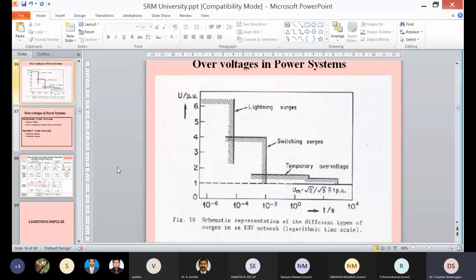In case of switching surge or switching transient, the rise of voltage will be in the range of 2 per unit to 4 per unit. In case of lightning impulse or lightning surge or lightning transient, the rate of rise of voltage will be in the range of 4 per unit to 6 per unit. More than 6 per unit is also possible, but generally this is the range. What I'm trying to say here is temporary overvoltage means 1 per unit to 2 per unit, that is the ratio. Switching surge means 2 to 4 per unit in between. Lightning surge means 4 per unit to 6 per unit.